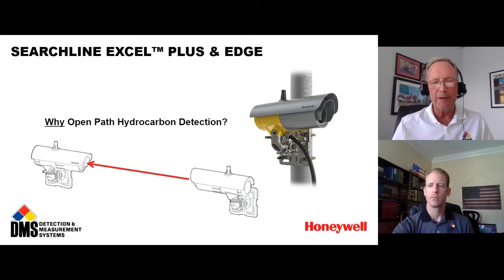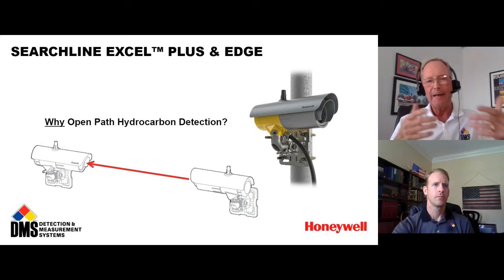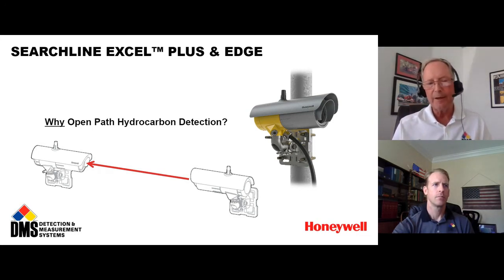And so when you have an application where you utilize both open path and point gas detectors, what you'll end up with is actually a gas detection system that utilizes fewer detectors, because you can replace a lot of point detectors with open path detectors.